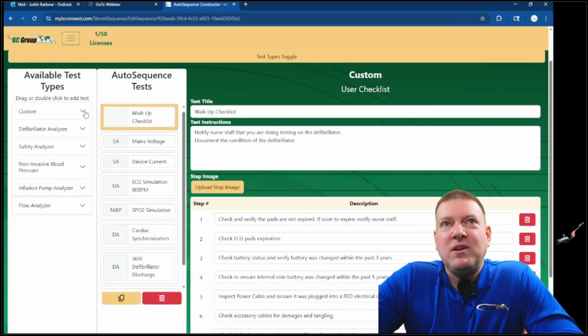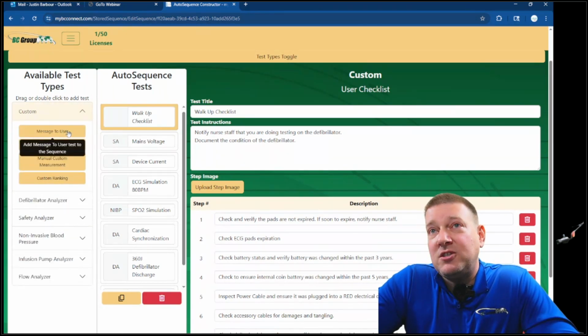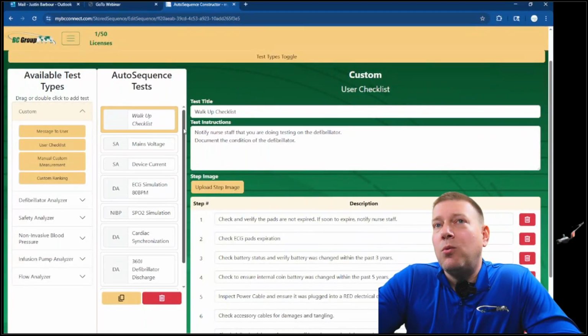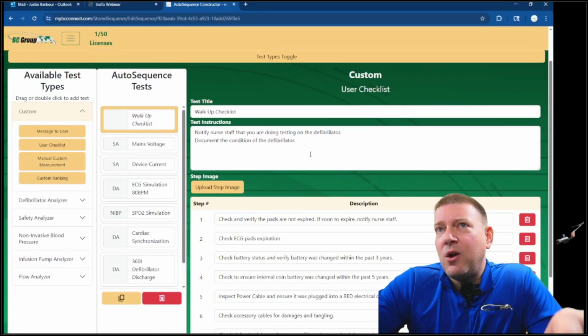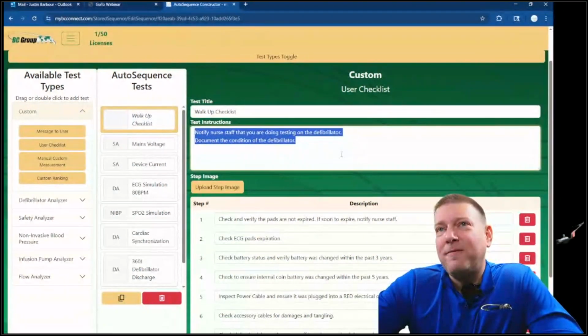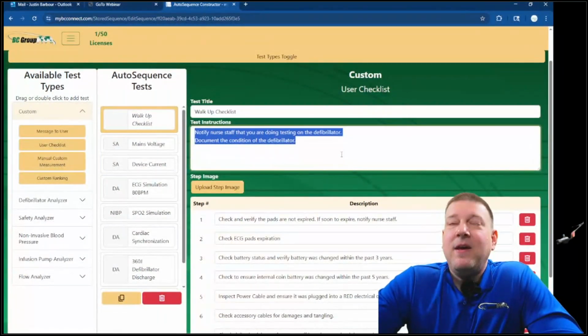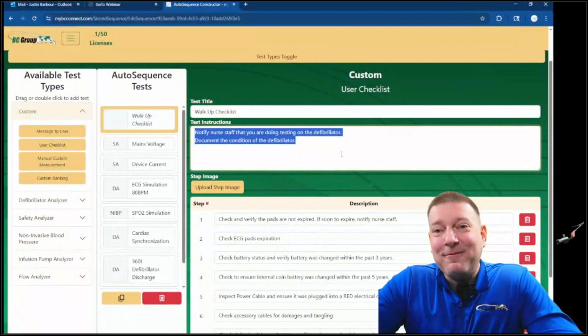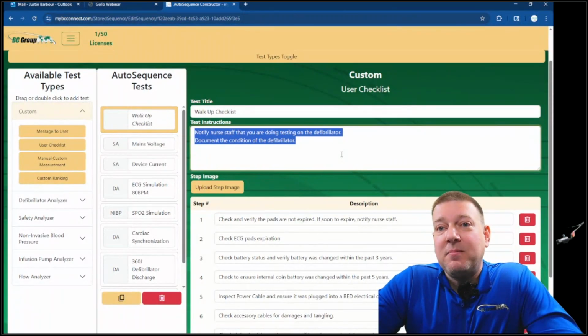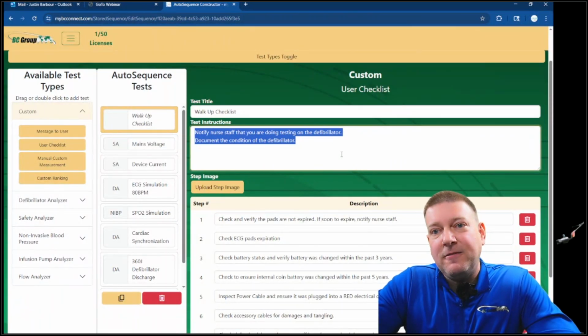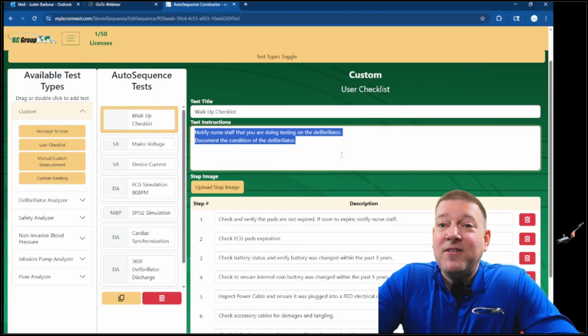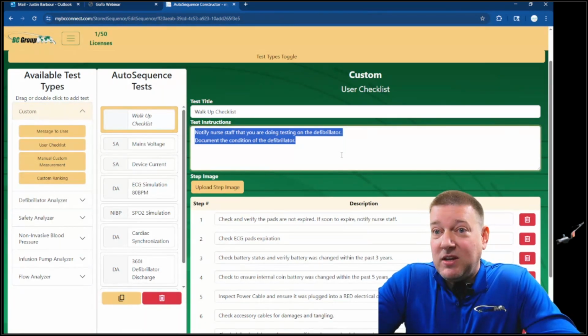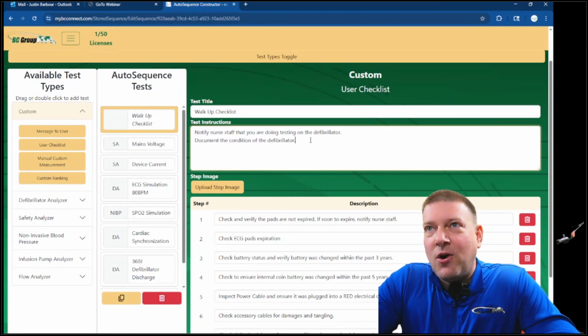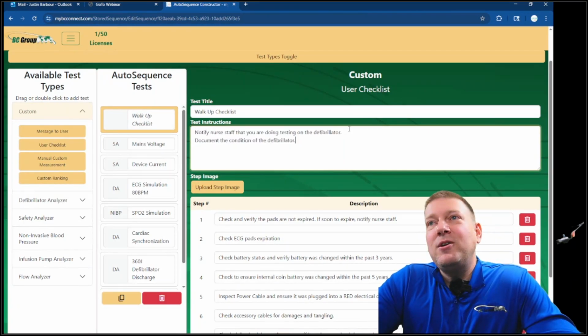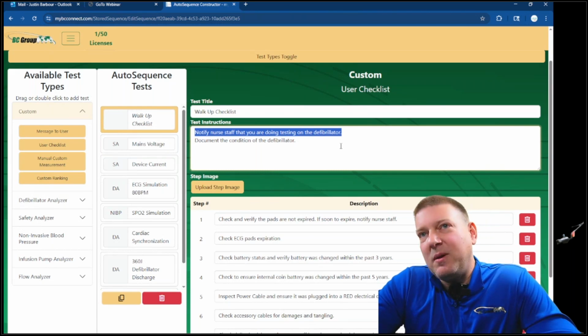When you create your own auto sequence, you can add notations to the user. Over here I did a walk-up checklist for a defib, and I put a note that says: notify nursing staff you're doing testing on the defibrillator. Why did I add that? Because if you're like me, you've probably made this mistake before, going down a hallway testing defibrillators, especially in an ICU, and the nurses come running when they hear the defibrillator charging because they think somebody's coding. I've made that mistake, and I don't want other people to make it, so you can put a notation like that to prevent it.